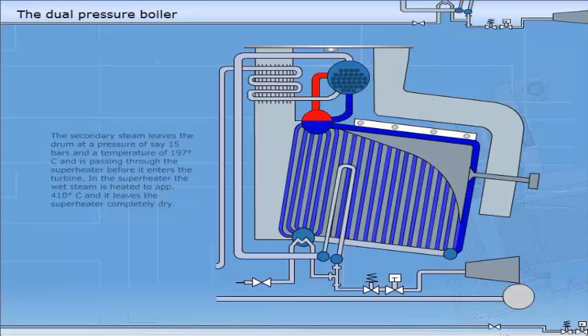The secondary steam leaves the drum at a pressure of, say, 15 bar, and a temperature of 197 degrees centigrade, and is passing through the superheater before it enters the turbine. In the superheater, the wet steam is heated to approximately 410 degrees centigrade, and it leaves the superheater completely dry.